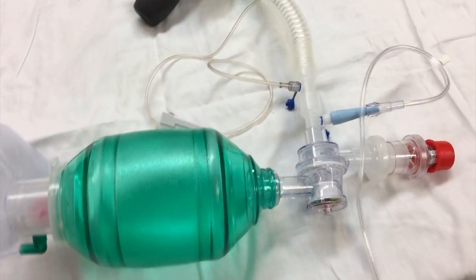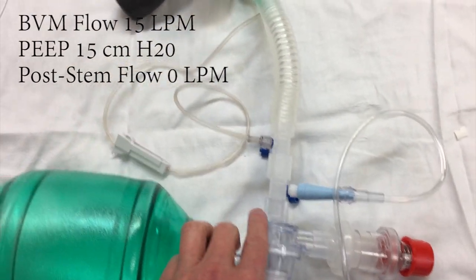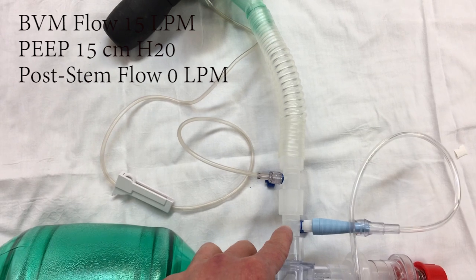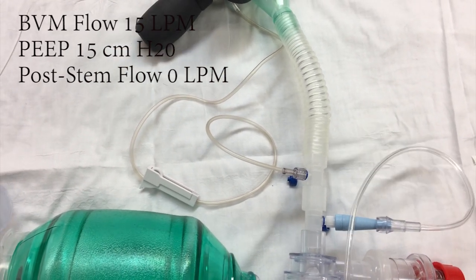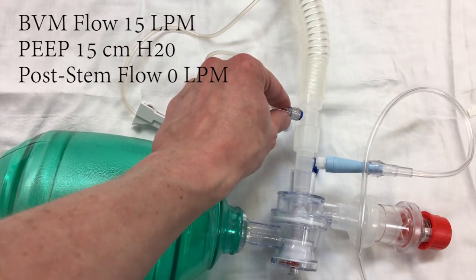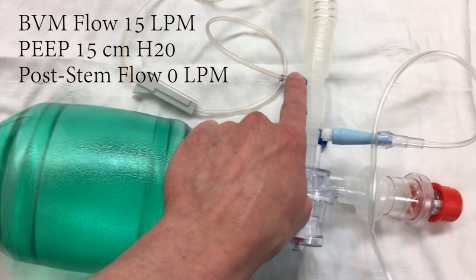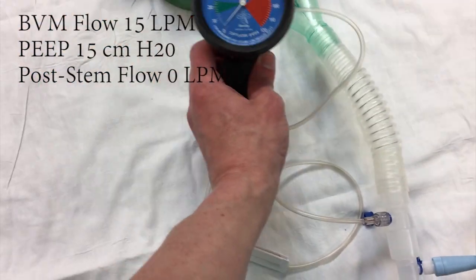All right folks, let me show you the setup. We have our BVM, currently hooked up to 15 liters per minute. It is going with a PEEP valve set to 15 centimeters of water at the stem. We have one end-tidal adapter going to oxygen on the wall, which is currently at zero LPM, and a second end-tidal CO2 port to allow us to go to our cufflator. There's the cufflator, and we have a test lung.